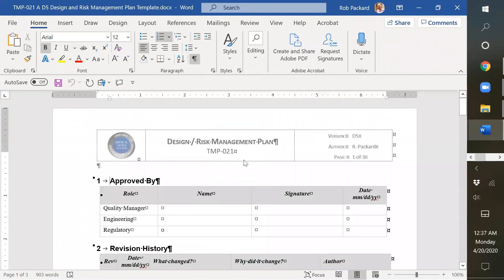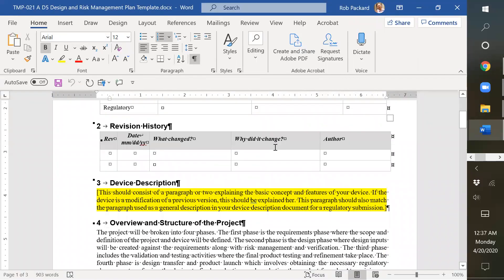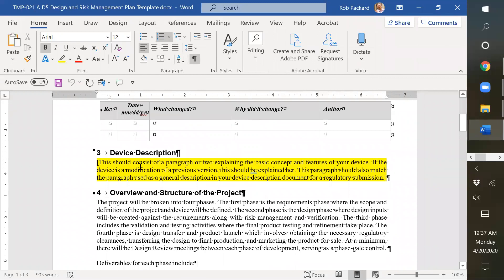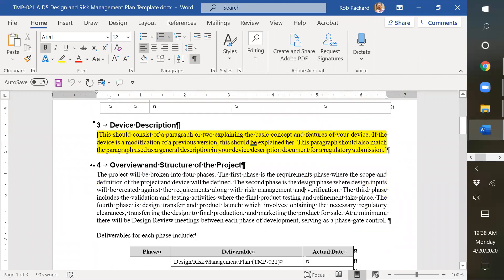Next item is the design risk management plan template. This is a device description that you would put in here that would be the same as what you would use for your design device description in a 510k summary, just the initial paragraph, the general description.